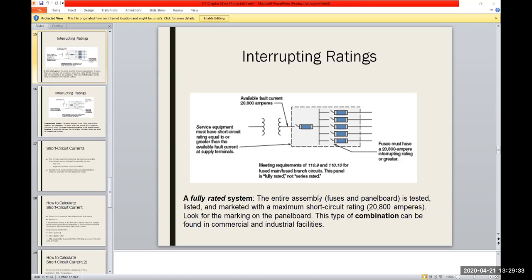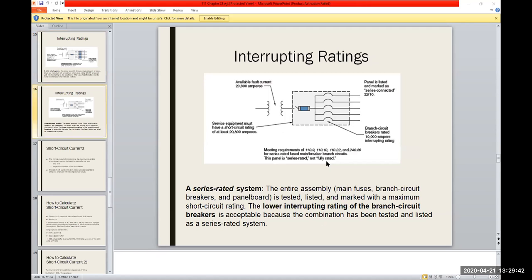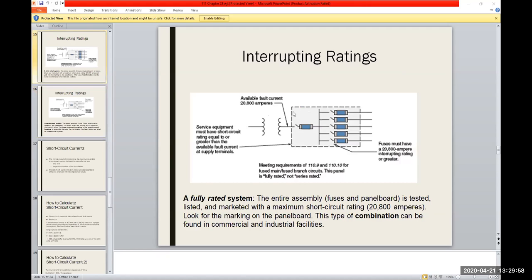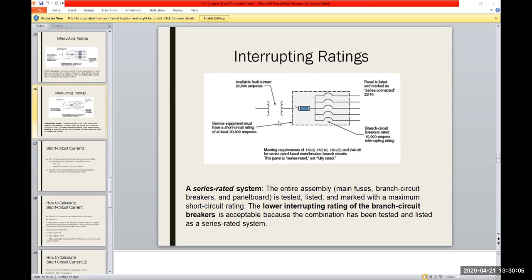But otherwise, you would just use a series rated one for most residences, unless the residence had a lot of toys in it, you know, saunas and that kind of thing. But usually the series rated ones are typical for a home, because you're never going to get that kind of current draw, really. I mean, if you look at this, what are our interrupt ratings? This one, you have fault current of 20,000 amps, okay? You're never going to have that.